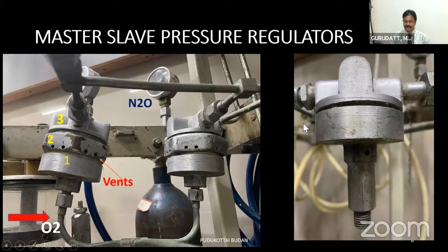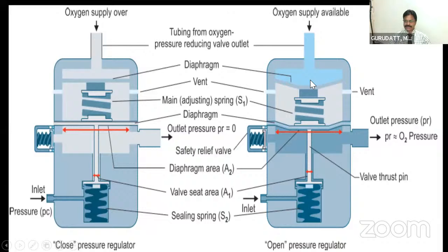I'm just showing you a diagrammatic representation of this master and slave pressure regulator. You can see this is the top chamber, chamber 1, which I showed in the photograph. This is the chamber where the oxygen is entering. Chamber 1 is separated from chamber 2 by a diaphragm. Now we can see the diaphragm here. Again, chamber 2 is separated from chamber 3 by another diaphragm. These 2 diaphragms are connected by a spring in between. The nitrous oxide has to flow through the inlet here, and then enter chamber 3.